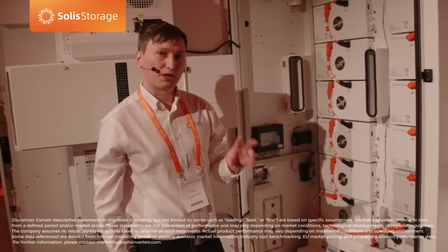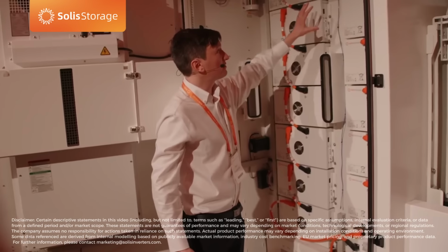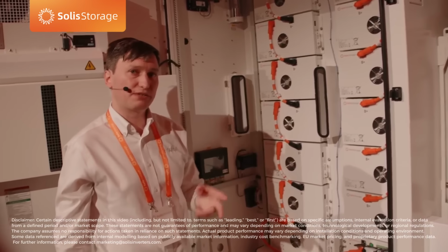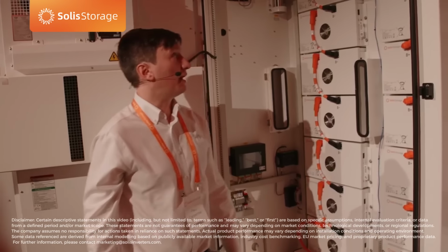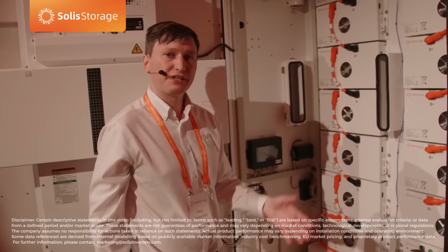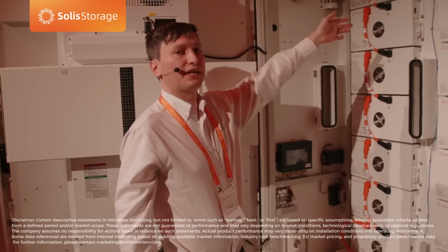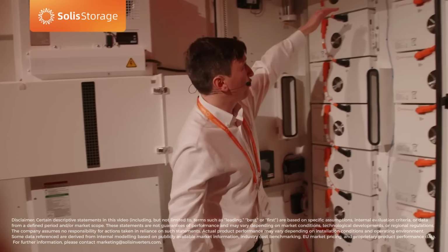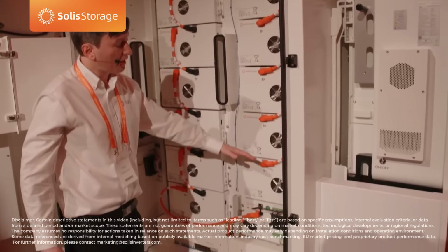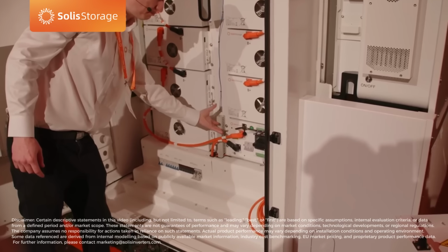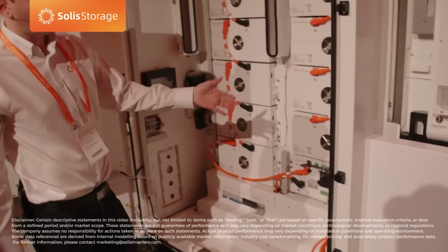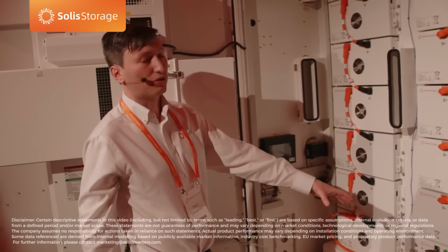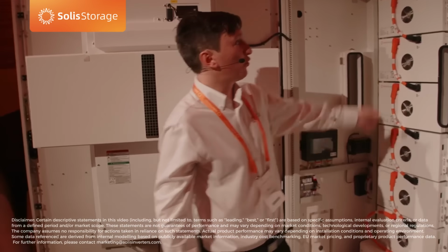The second core element I want to speak about is the physical batteries themselves. Inside each pack is 20 cells, 314 amp hour cells. There's 20 cells in series, making up your 64 volt, 20 kilowatt hour battery pack. There's 13 of those packs arranged in series, giving you this 14th pack - this white box that looks like a battery is not a battery, it's our high voltage box. Very, very important component in the system. Your 13 packs arranged in series give you your 832 volt solution, and that is the 261 kilowatt hours battery cabinet.